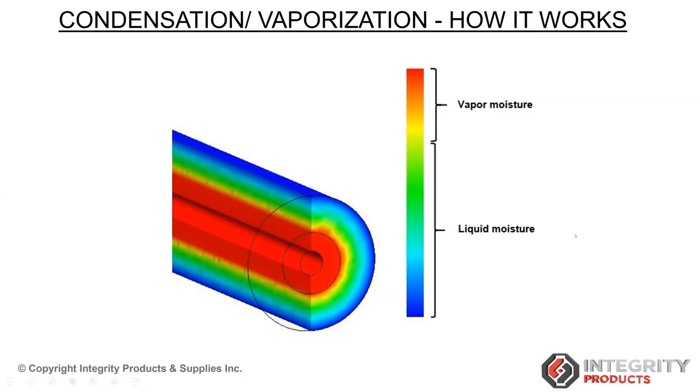Awesome. So we had one other person asking about termination gaskets and what sizes they're available in. Yeah, I think we may have skipped over it quickly during the presentation, but we make them bespoke. For every pipe size and every insulation thickness, we can make the gaskets to suit. We've even done some very large ones, in excess of 30 inches on 30-inch pipe. And we can make them from a very small size to a very large size, including for low-profile insulation systems like aerogel blankets. So they're made bespoke, and we can make them in any size which is required.